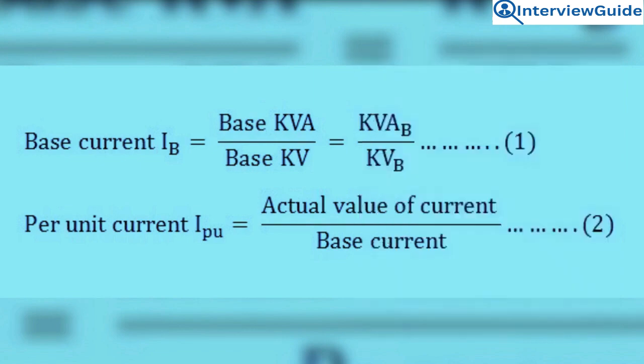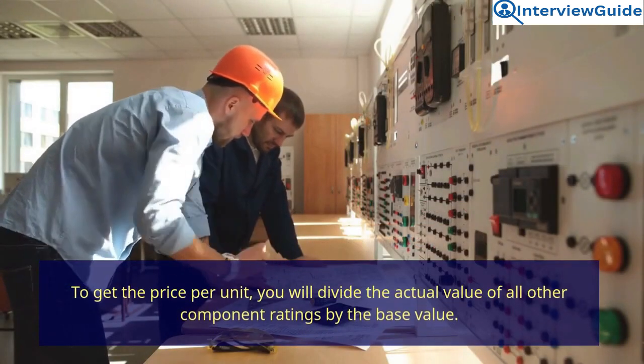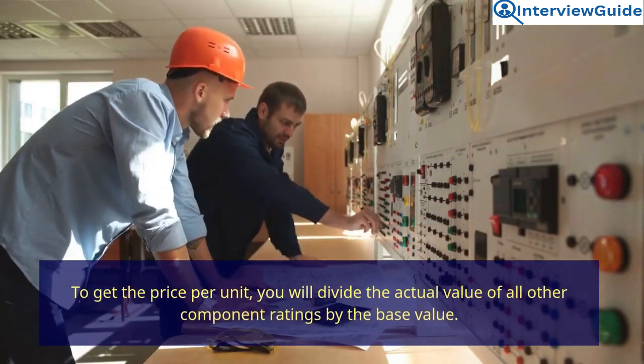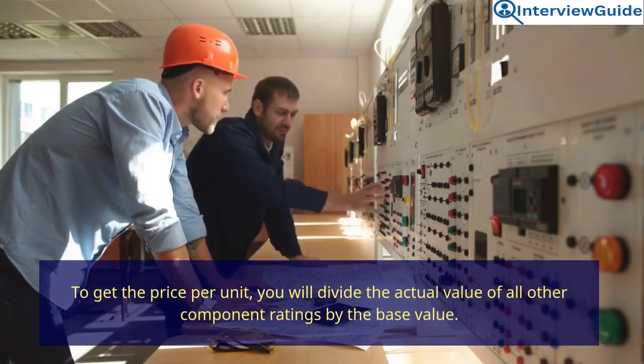In this case, the largest MVA and KV ratings are generally taken as the base values. To get the price per unit, you will divide the actual value of all other component ratings by the base value.